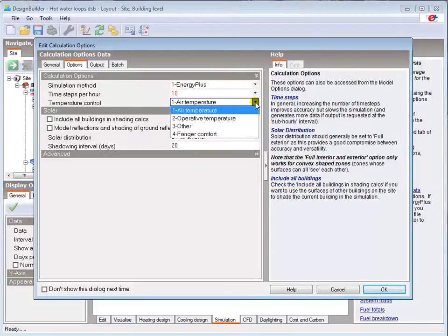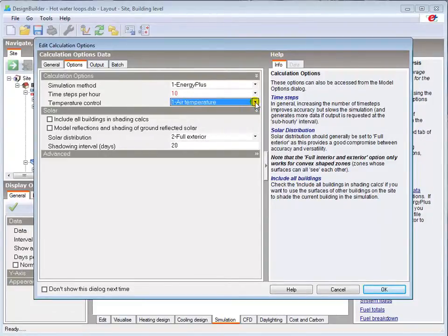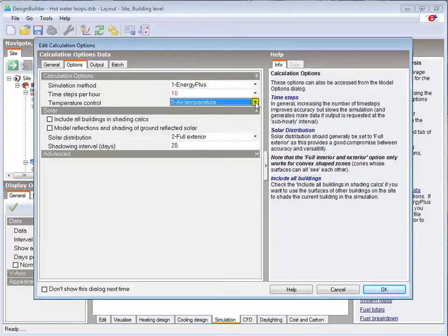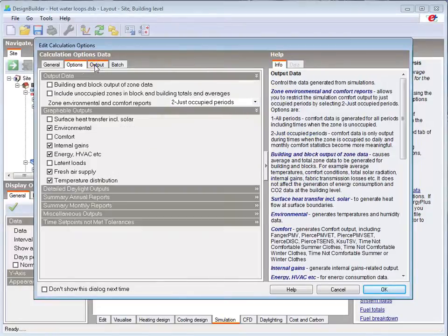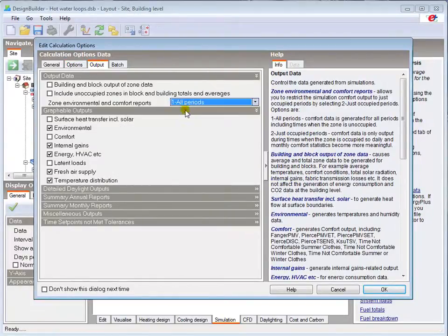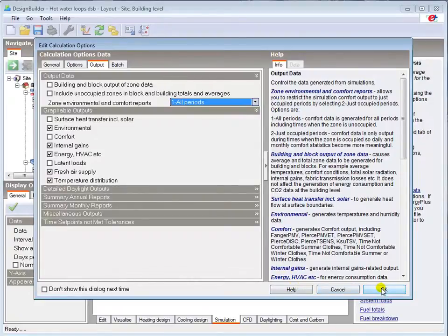I'll leave the temperature control set to air temperature, as this is not a highly radiant system, and there are no other highly radiant features in the building, such as poor insulation or large expanses of glazing, except in the reception, which would need to be considered. I'll report on all periods, and then run the simulation.